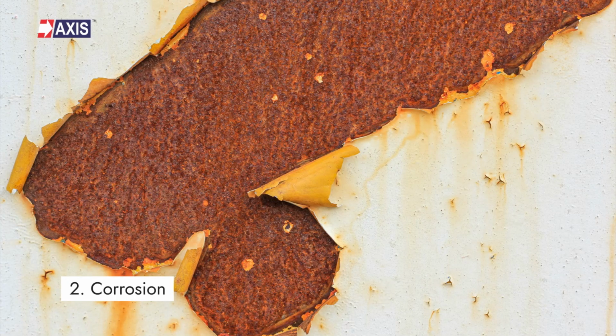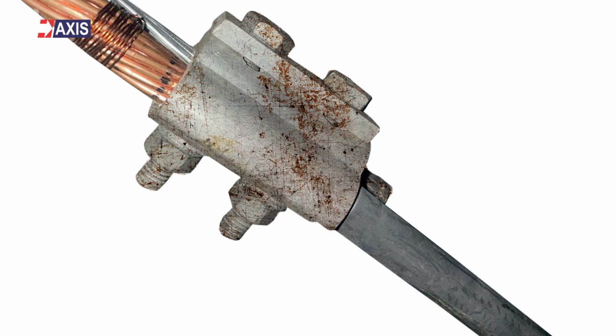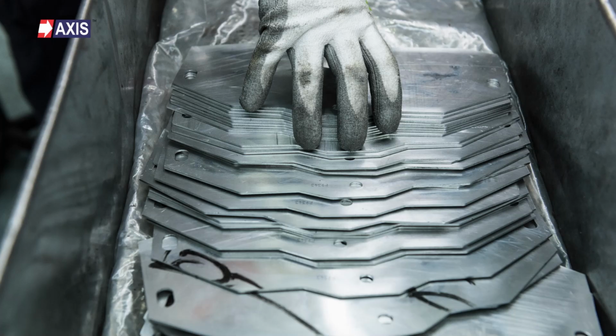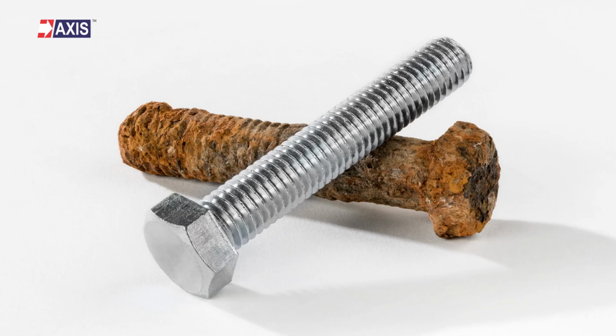The second is corrosion. Corrosion can lead to increased electrical resistance, causing heat buildup and potential failure. It also weakens the mechanical strength of the clamp, leading to breaks or cracks. One technique adopted to avoid corrosion is tin plating. Also known as tinning, it's an industrial process where the surface of the metal object is coated with a thin layer of tin. This plating helps resist corrosion and ensures good electric performance.